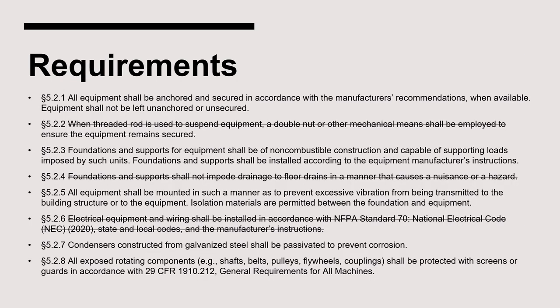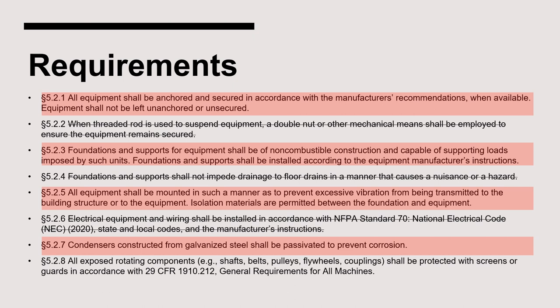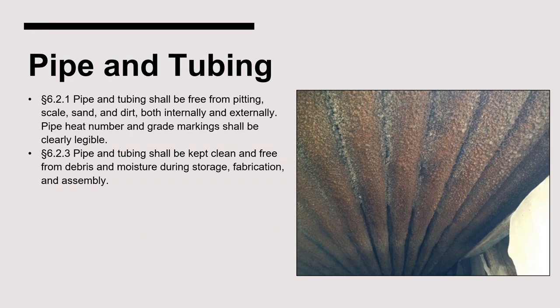The requirements on this page are applicable to all ammonia refrigeration equipment, though select items do not pertain to condensers. Here is a quick rundown: all equipment must be anchored and secured. Foundations and supports must be non-combustible and designed for the load they will carry. Equipment must be mounted to prevent excess vibration. Condensers must be passivated to prevent corrosion. Exposed rotating components must be protected. Pipe and tubing requirements for condensers include keeping the pipe and tubing free from pitting, scale, sand, and dirt, and shall be kept clean during storage, fabrication, and assembly.